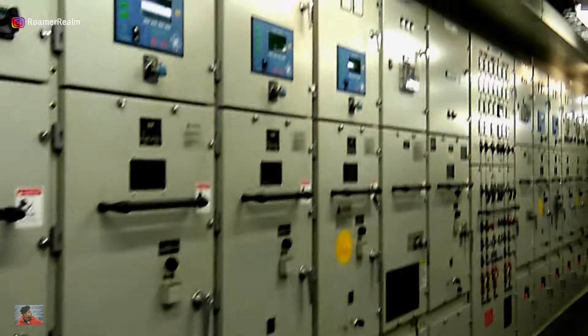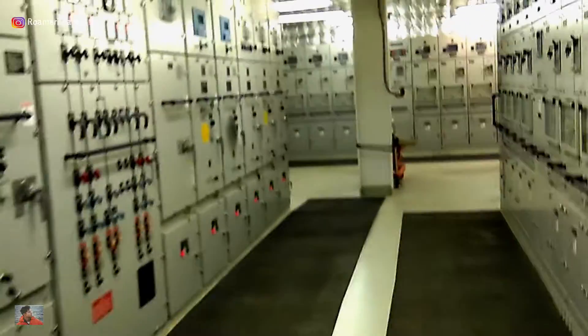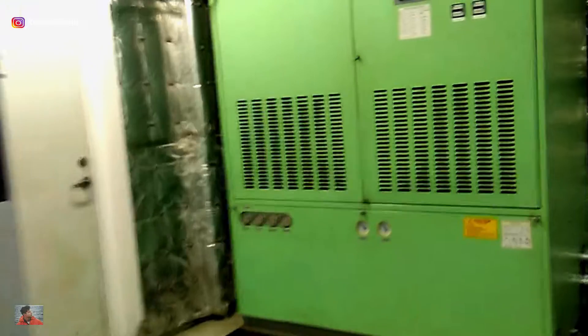Of course, it can vary from one ship to another depending on the type of ship, the type of heavy consumers, machinery etc. High voltage systems as a safety measure are supposed to be away from the engine control room, and the room has to have its own separate cooling system to keep the components cool and free of moisture, especially when the ship is trading in humid areas.